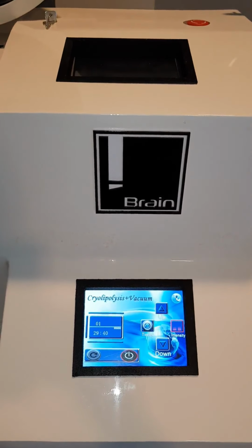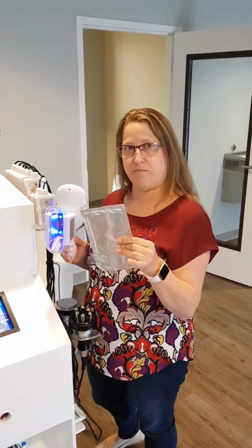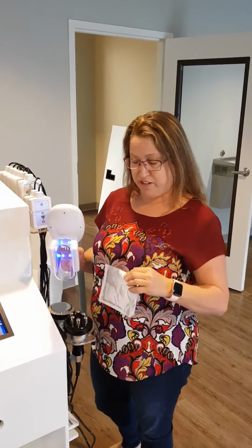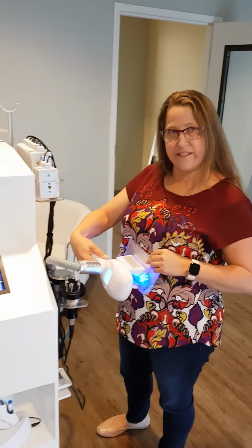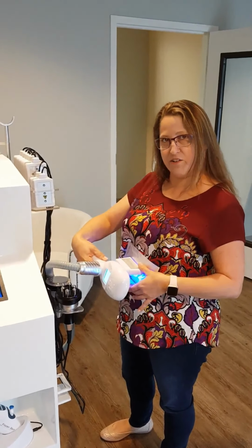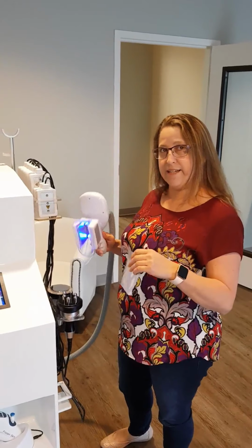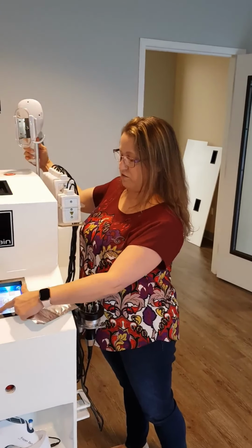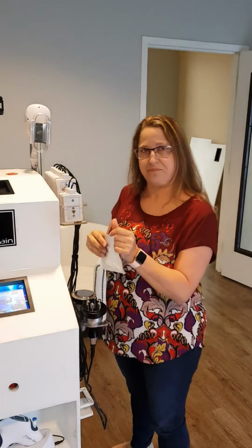Prior to using this on the patient, you will need to use the anti-freezing membrane to avoid skin necrosis to the treated area. To treat, you would apply this directly to the skin. The suction starts immediately. For settings and timings on different types of fat, you can see that in our instruction manual.